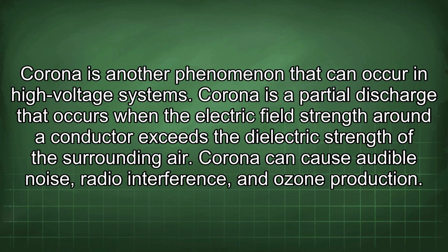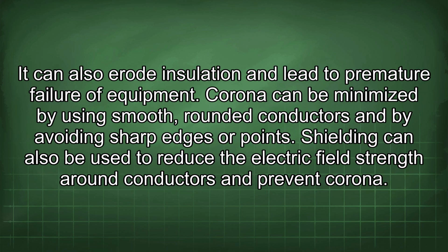Corona is another phenomenon that can occur in high voltage systems. Corona is a partial discharge that occurs when the electric field strength around a conductor exceeds the dielectric strength of the surrounding air. Corona can cause audible noise, radio interference, and ozone production. It can also erode insulation and lead to premature failure of equipment. Corona can be minimized by using smooth, rounded conductors and by avoiding sharp edges or points. Shielding can also be used to reduce the electric field strength around conductors and prevent corona.